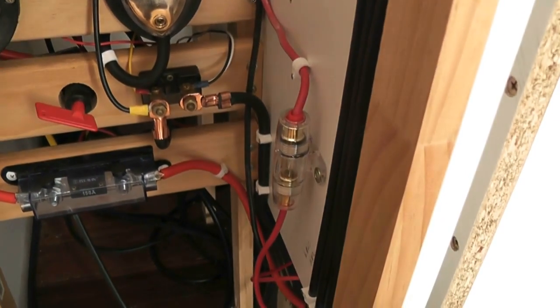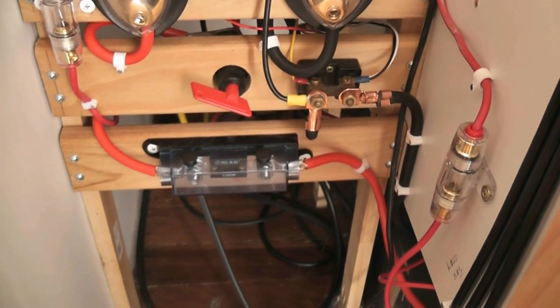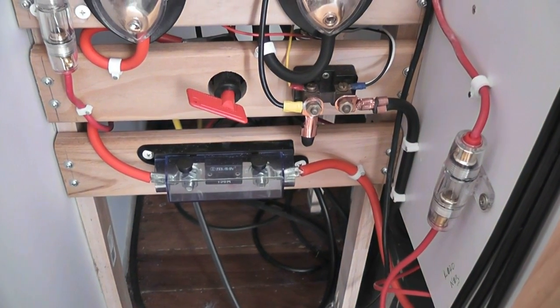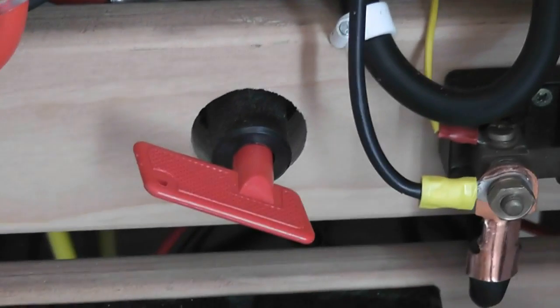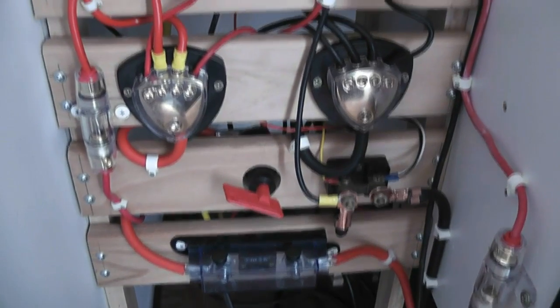If we now look at the DC side of things, the main feed from the battery comes through the system main fuse. It's a 160 amp. That then comes around and comes up to that red key, which is the main on/off, so I can shut down all of the DC at the same time.